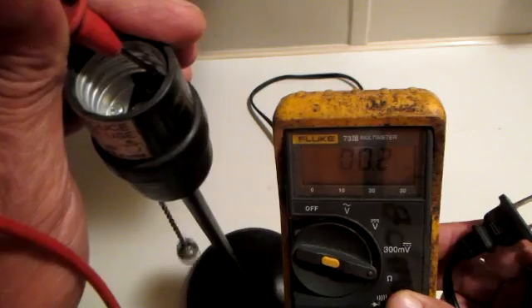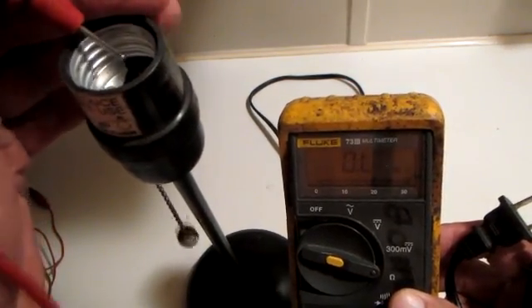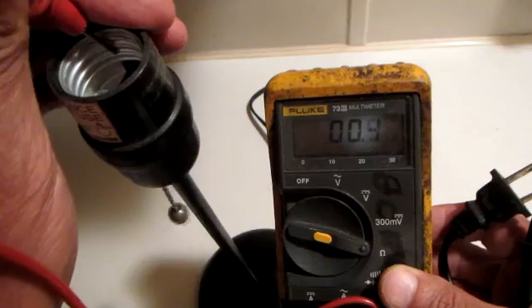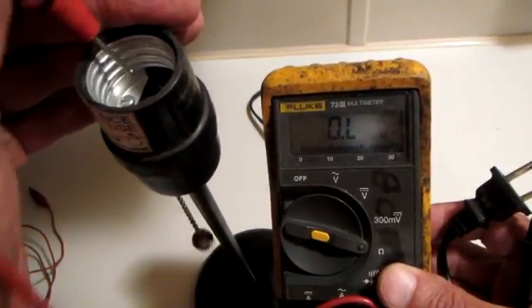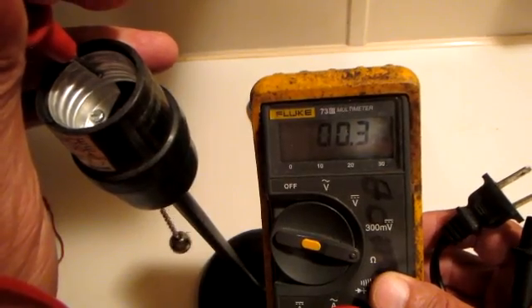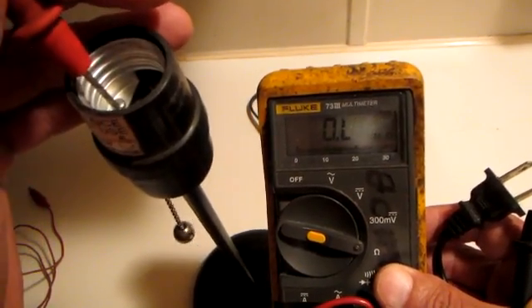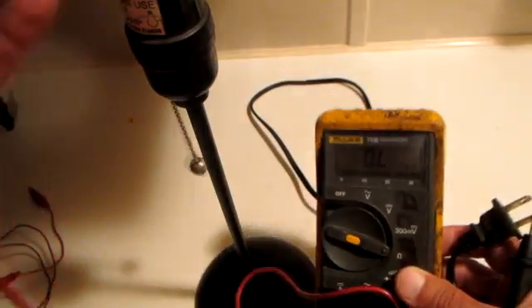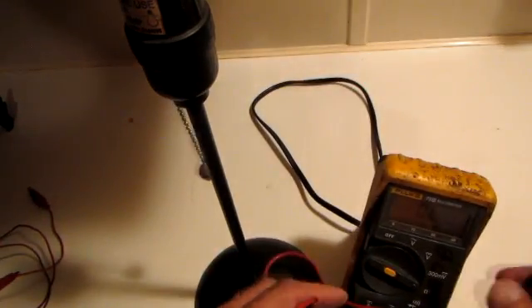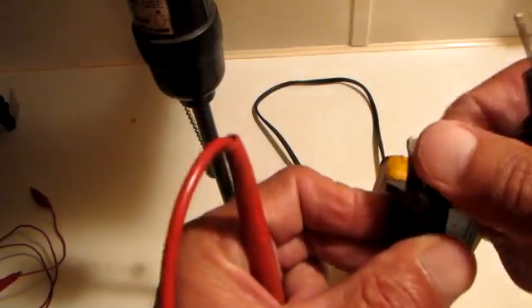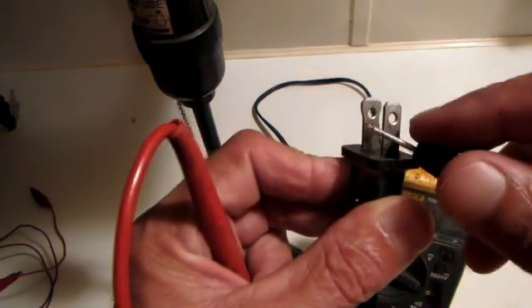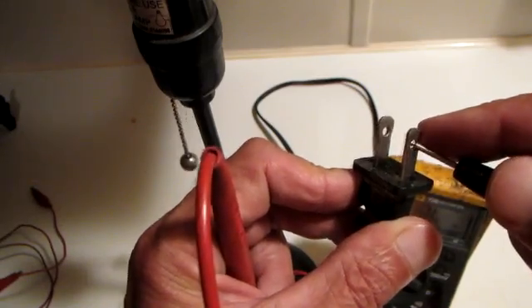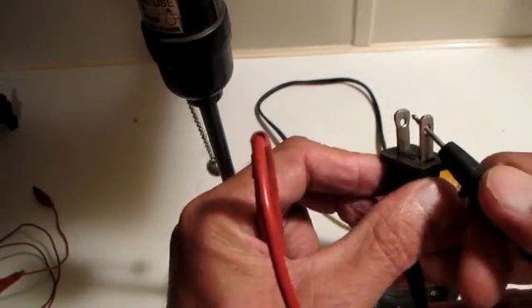We have good contact here. You also might want to touch the center probe to verify you have a dead open. And there we have good contact, we have good open, and that side of the plug is hooked up properly. Ground side is going to the ground side of our socket. Now we're going to go to the smaller probe on our plug, that should be the hot side. This should be connected to this center contact of our socket.